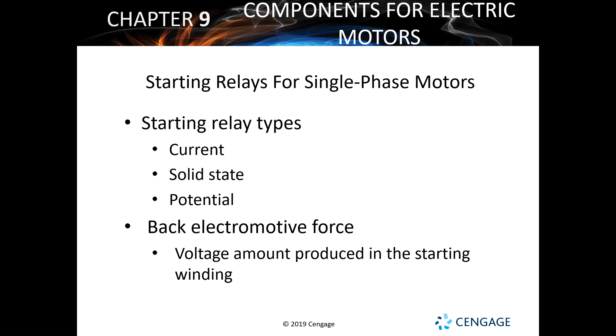So current or amperage relays, they're your most basic style for a single phase motor. It does the easy thing. It's going to sense the current or the amperage of the motor, and that's when it's going to decide when to disconnect that starting amperage, or the start winding. Because again, remember, starting amperage is greater than the running amperage. Your running amperage is stated as your FLA. That's pretty much all you're going to be seeing it written as nowadays, is the FLA of a motor.